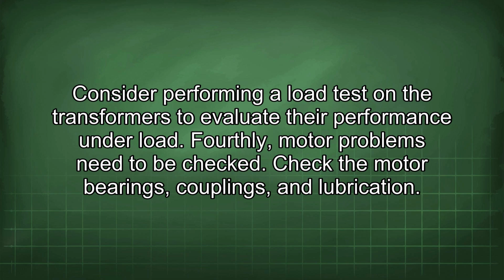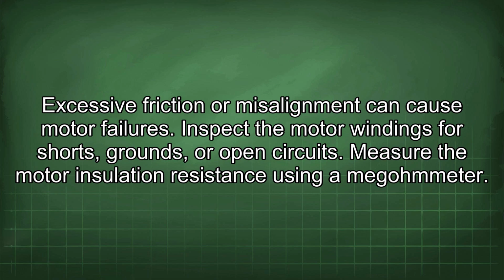Fourthly, motor problems need to be checked. Check the motor bearings, couplings, and lubrication. Excessive friction or misalignment can cause motor failures. Inspect the motor windings for shorts, grounds, or open circuits. Measure the motor insulation resistance using a megohmmeter.